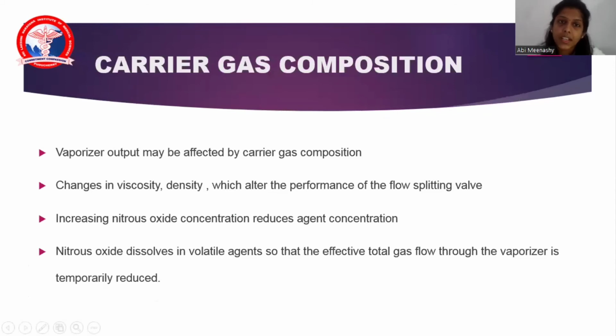Okay. Next is carrier gas composition. Vaporizer output will also be affected by carrier gas composition. It changes viscosity and density, which alters the performance of the flow splitting valve. Increasing the nitrous concentration will actually reduce your agent concentration. Your nitrous is your carrier gas.